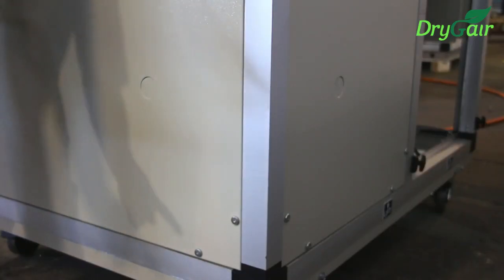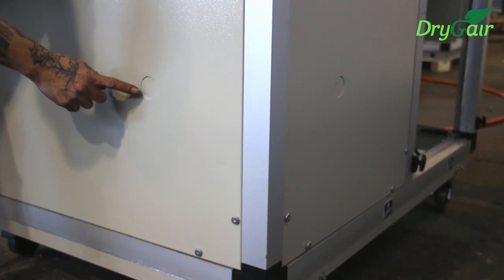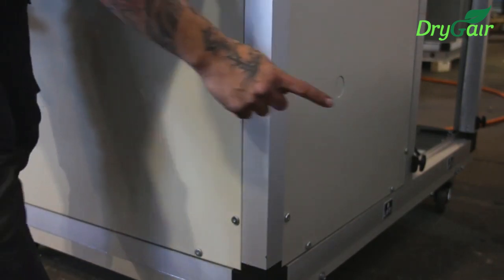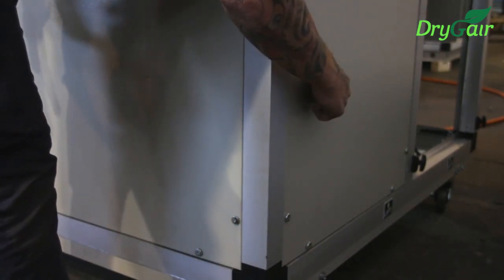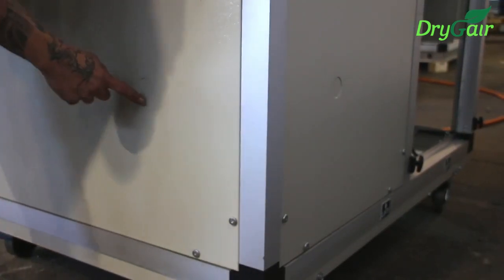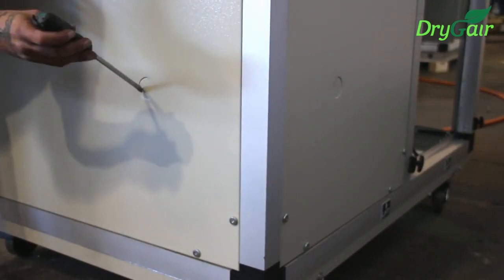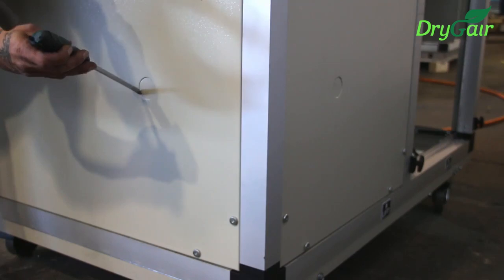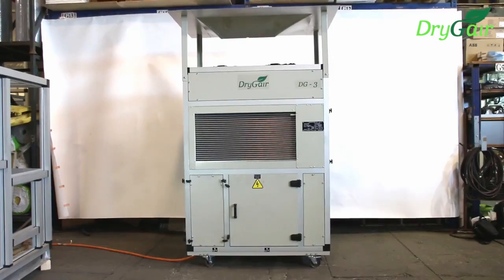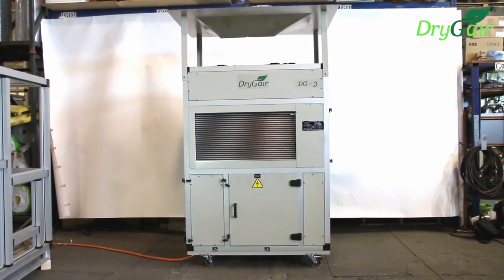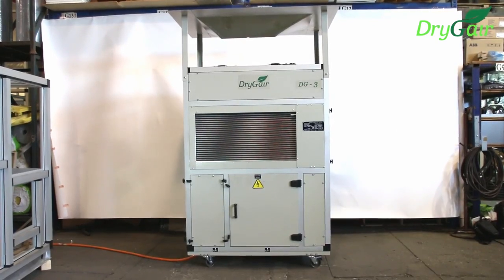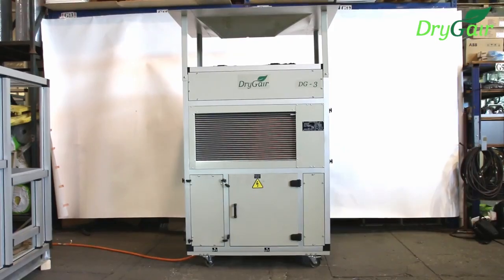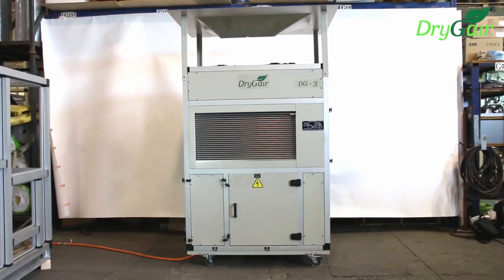You also have the option of routing the drainage pipe out of the side cover or rear cover of the unit. You will find a pre-made circular cutout on these covers that can be removed simply with the use of a screwdriver and hammer. Once the cutout is out, run the tube through the hole. Once the tube is in place, return and secure the unit rear cover and route the drainage to the water collection location.